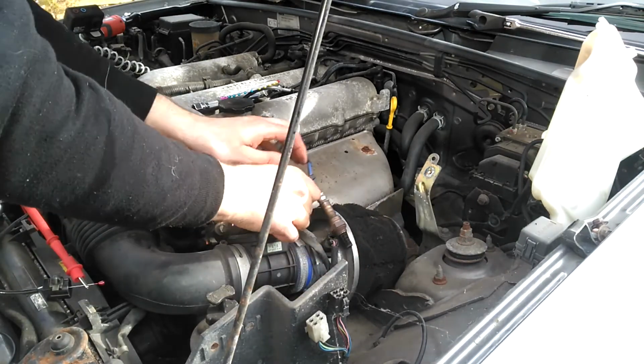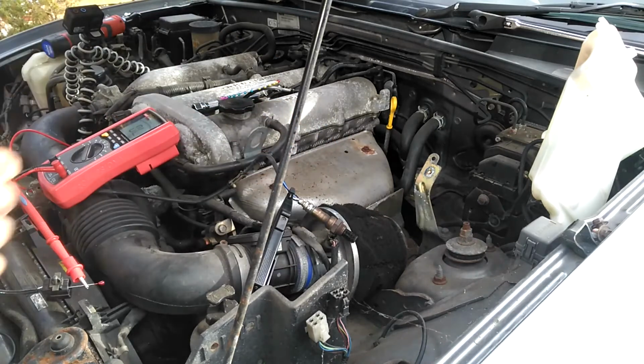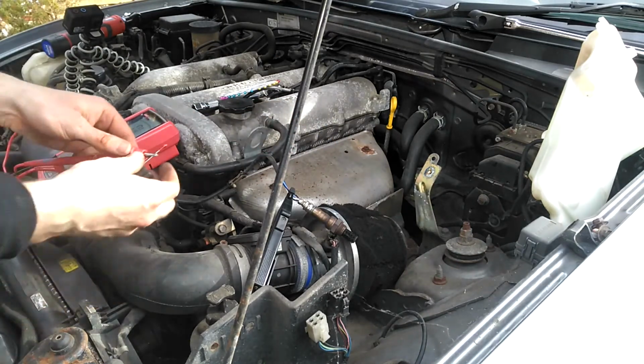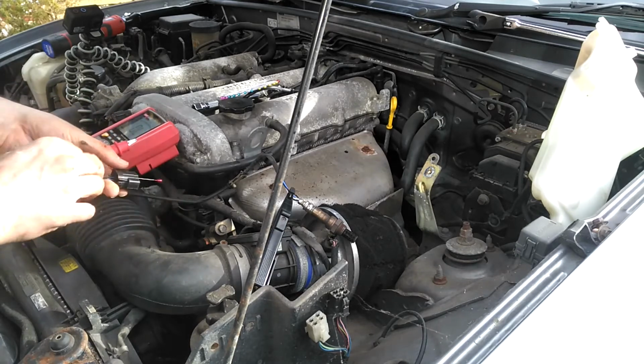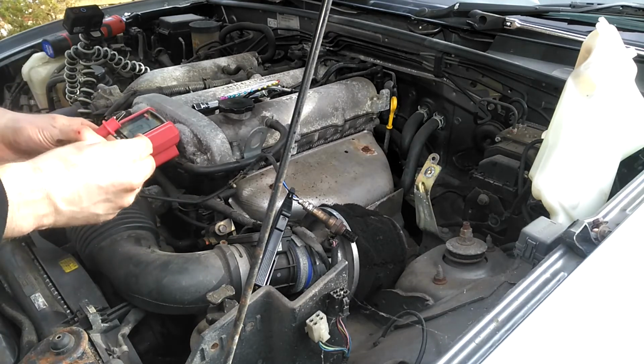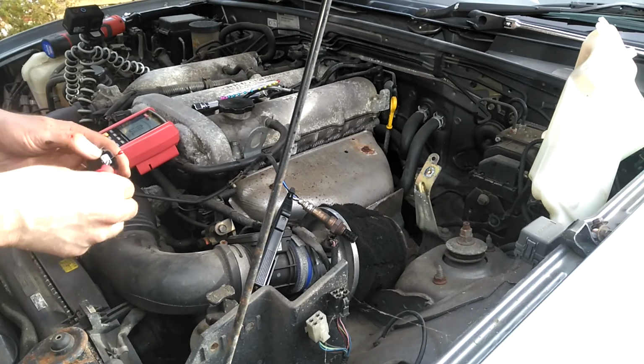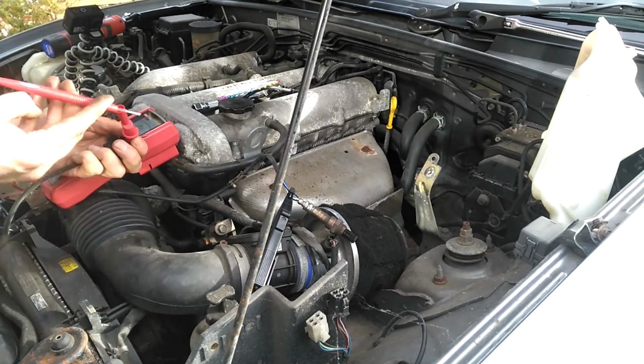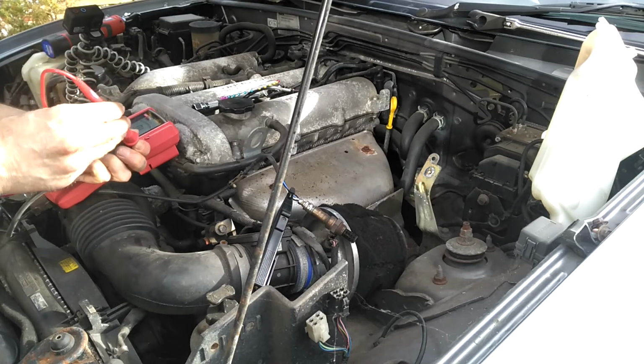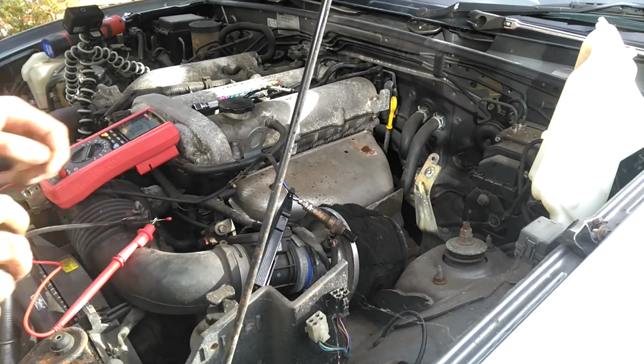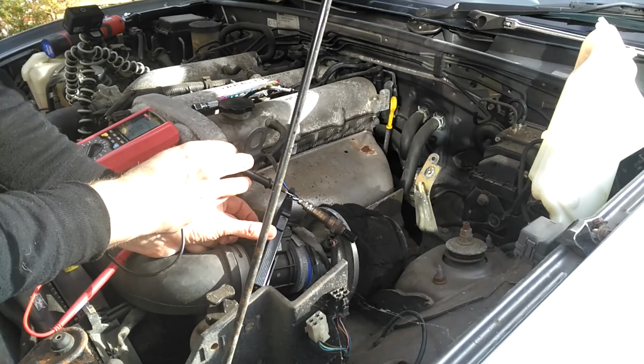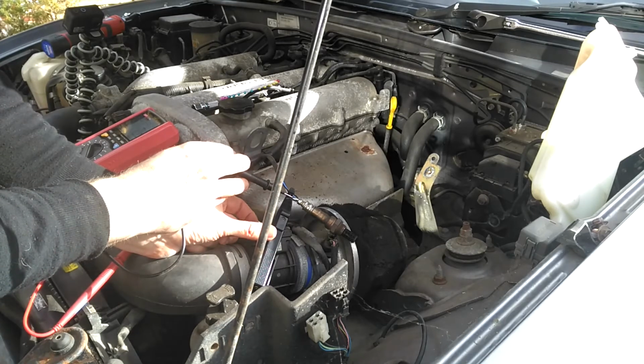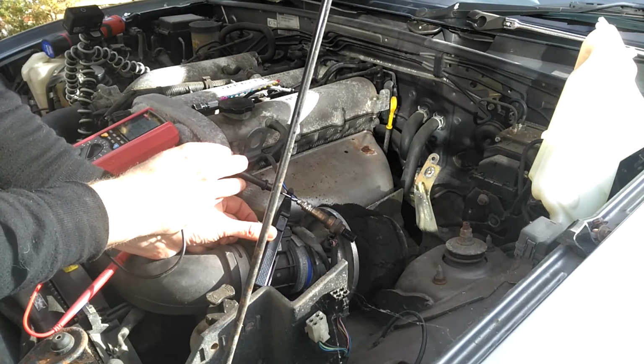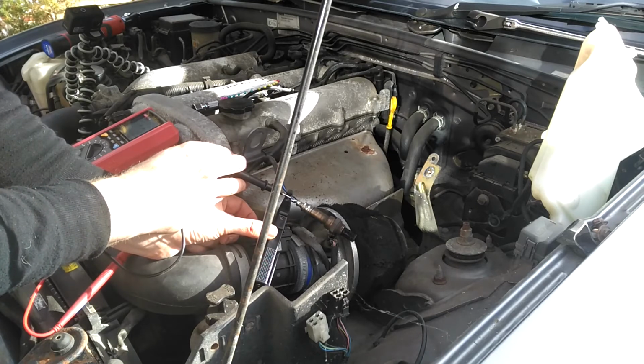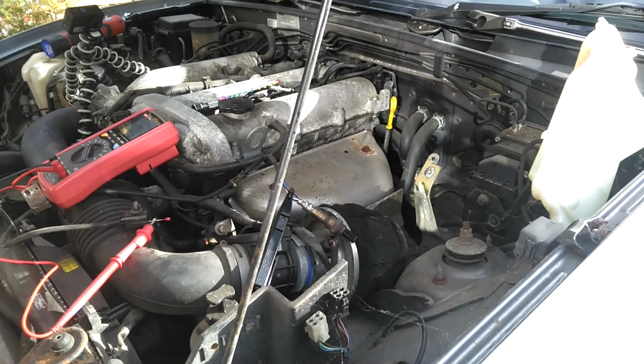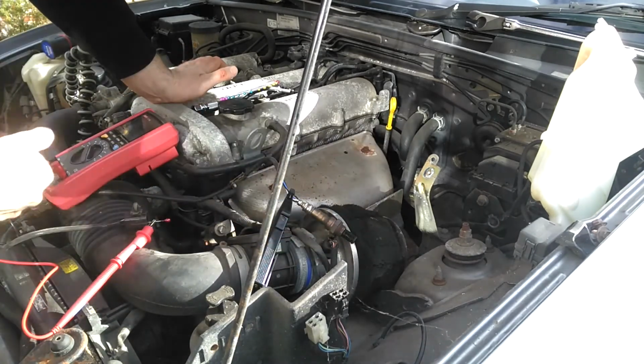So, leaking a bit. And what we're going to do, we'll swap it over to the second black wire here, plug it in, connect it up, put the wire back in, and again we can touch it up here if we want to do. Oh, come on. There we are. So what that's telling us, there isn't a break between here and the connector, so we haven't got any wiring issues.